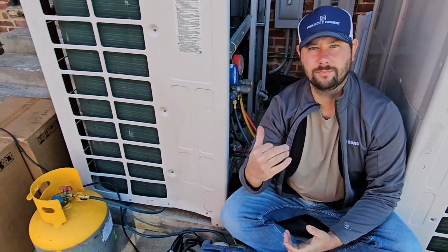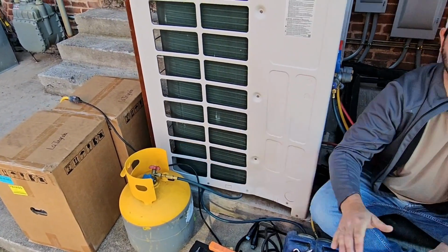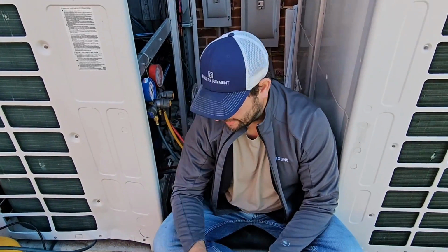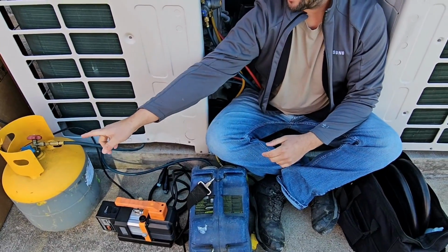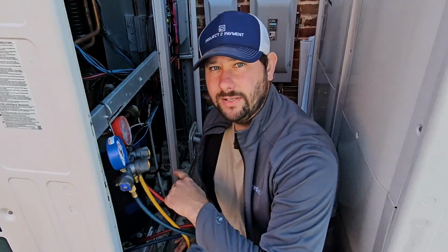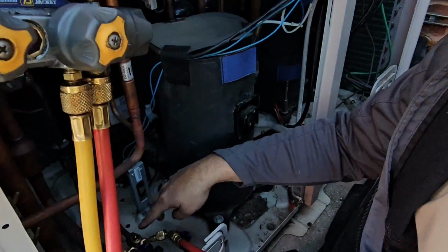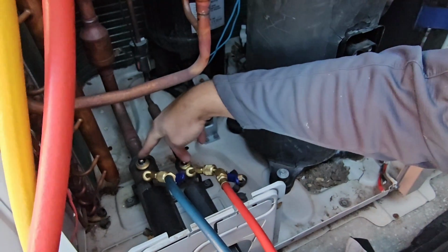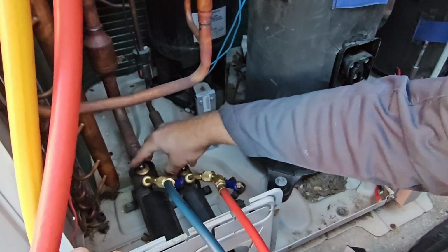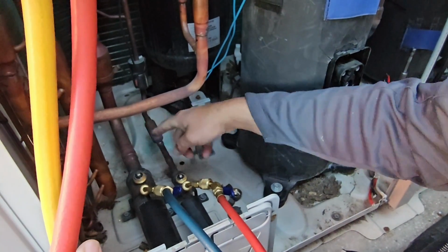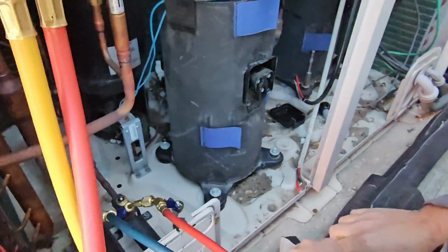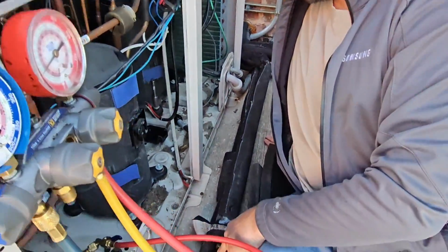Today we're replacing some compressors on the Samsung DVM unit right beside me. I've got the panels off. I've got the 2 compressors that we are going to be replacing, and I've got the recovery machine and recovery tank. I really like the fact that inside the Samsung DVM condenser, or outdoor unit, we've got isolation valves right here. So I'm glad that we've got these service valves. I've got them open and my gauge is connected, but I've also got isolation valves right here.